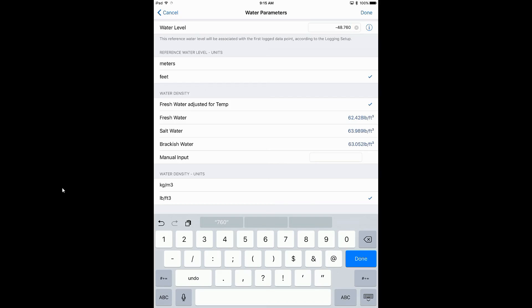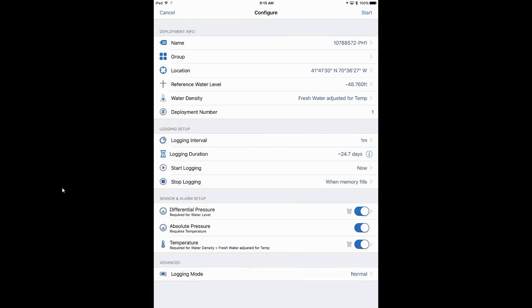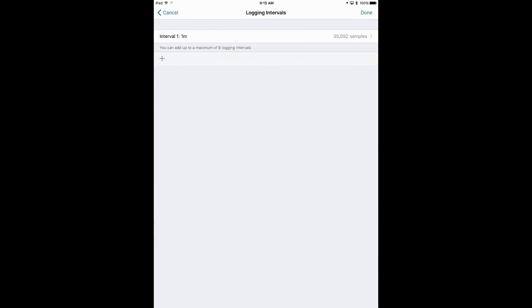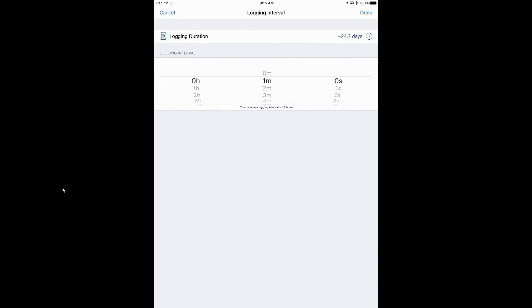We'll tap on Done. Now we have our reference water level entered. The logger counts how many times it's been deployed and there's no limit to that number. Below that, under Logging Setup, this is where we set our logging interval. I want to set it to a five-minute interval for this application, though that will vary from application to application depending on where you're deploying.